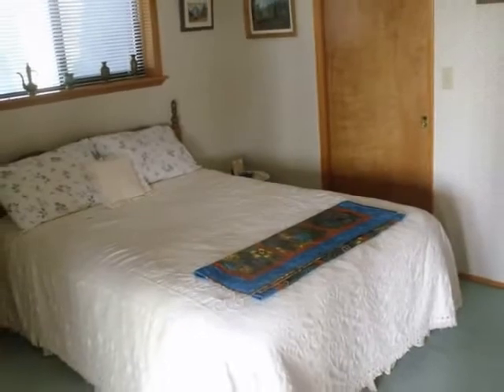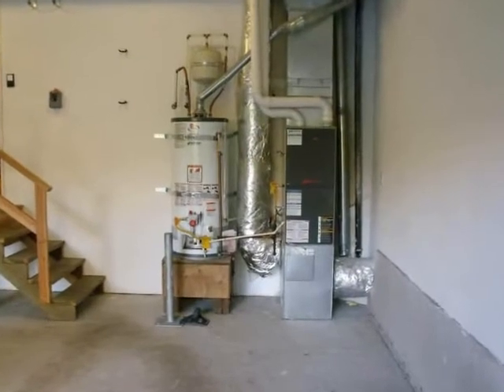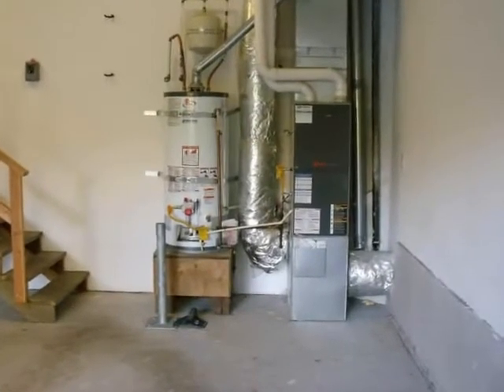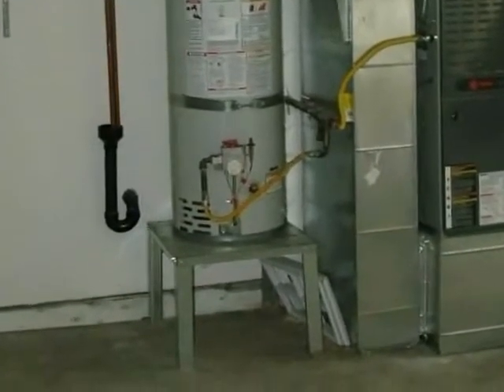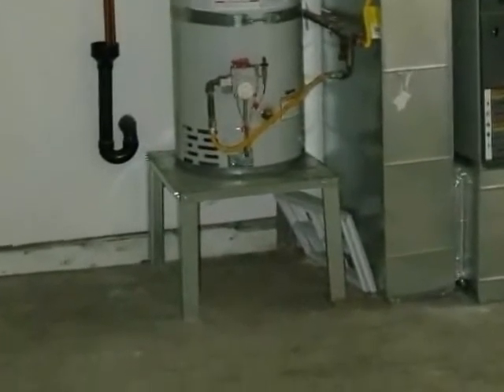Here are some additional safety tips. A garage may not lead directly into a bedroom. Heating appliances, unless they're equipped with today's sealed combustion chambers, must be elevated at least 18 inches off the garage floor to guard against potentially igniting flammable vapors.